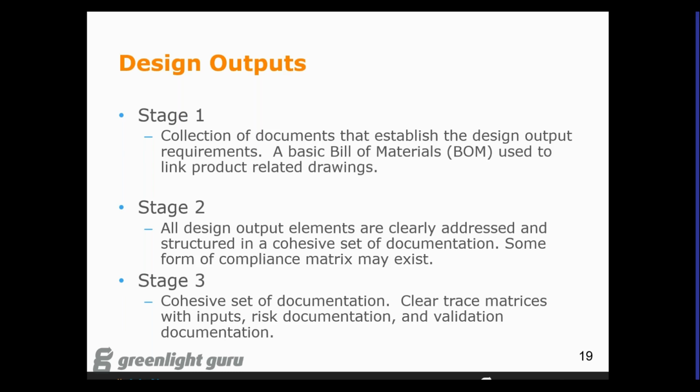Now, what I've seen in the most mature systems and processes is a really clear trace matrix that links not only the design inputs and the outputs, but also links to your verification and validation documents and your risk documentation.